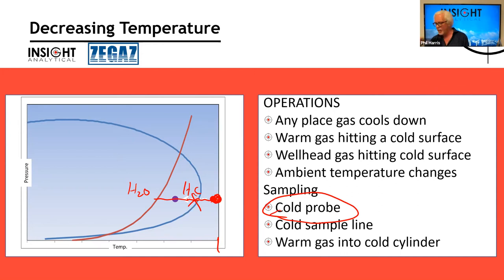And so anytime we have cold probes or cold samples, even if we're going to pull a manual sample, in one of these sample bombs sort of things. If this has been sitting in the back of my truck and it's cold, it's minus 40 in Canada, and I take it out to the pipeline and try to pull a sample, well, as soon as it hits the cold metal, it starts to condense in the cylinder. So now I have more liquids in the cylinder than I should have. Send it to the lab and they go, oh, you've got a big dew point problem. Well, it's because my cylinder was so cold, it condensed out extra liquids. So decreasing temperature is one of the other things that causes us to hit a dew point.